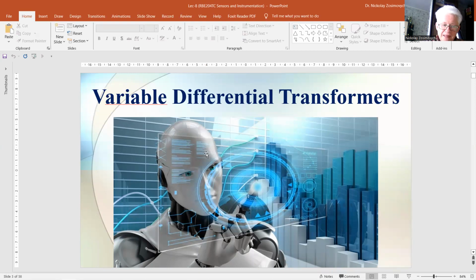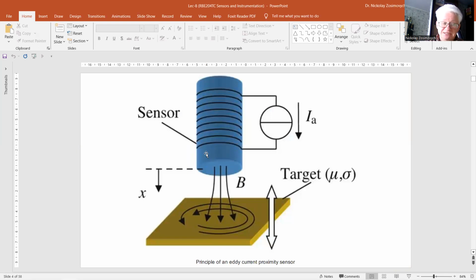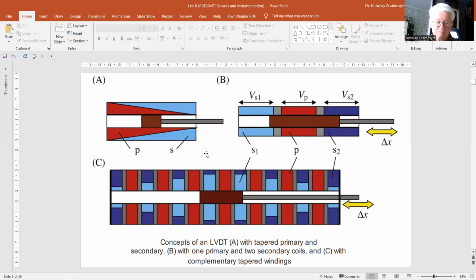Just a coil with a movable core as a displacement sensor, as you can see in this figure, shows strong non-linearity even when configured in parallel. A much better linearity we can obtain with a transformer with a movable core, the linear variable differential transformer. As you can see here at the bottom, the abbreviation is LVDT, a linear variable differential transformer.